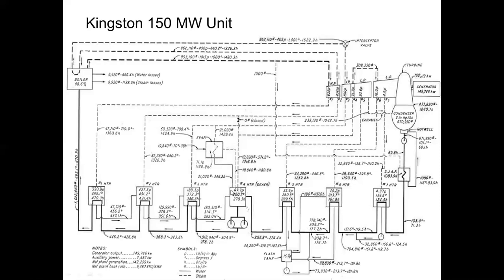Over here is a boiler showing 88.6% efficiency, burning pulverized coal. They take coal, grind it up into the consistency of face powder, and blow it through coal pipes in the burners, where they're also blowing hot combustion air. They fire it tangentially from the corners of the boiler to form a swirling fireball in the furnace portion, which transfers heat into the boiler tubes where steam is generated.